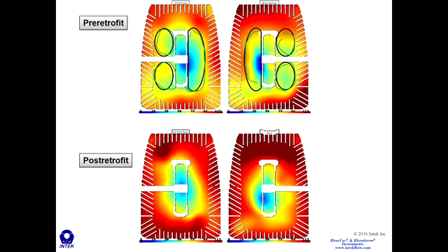So we worked around the existing tubes, and you can see here the dramatic improvement in the airbound zones post-retrofit. Again, if you use that technique where you identify the yellow color to identify the boundaries of this airbound zone, you can see how big it is pre-retrofit and how it's dramatically reduced post-retrofit.